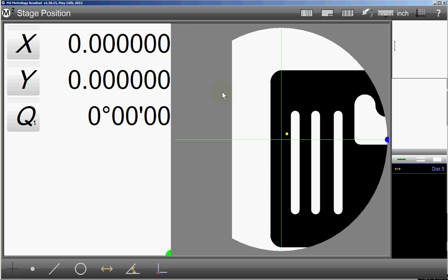So for our calibration, there's 2 ways to enter the error correction. First is take a measurement and have a length measurement displayed in this results window over here on the right, and then change the nominal value of it and import that into your error corrections. That's the way they tell you in the manual. There's another way also where you can create this distance yourself using distance and putting in values for the distance, and then you can import that as if you measured something. So let's do them both. We'll take the first one.